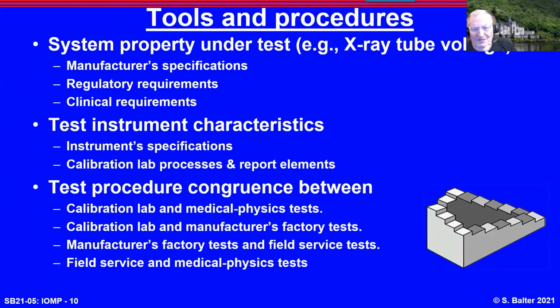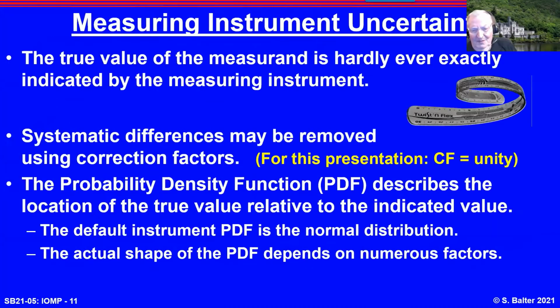There's another series of mismatches or lack of congruence between the calibration lab, how the manufacturer tests at the factory. A third layer between the manufacturer's factory tests and field service, and then field service and medical physics. It's sort of an endless Escher stairway to get these in congruence. Instruments have uncertainty. For the purpose of this presentation, I'm assuming that the correction factor is almost unity.